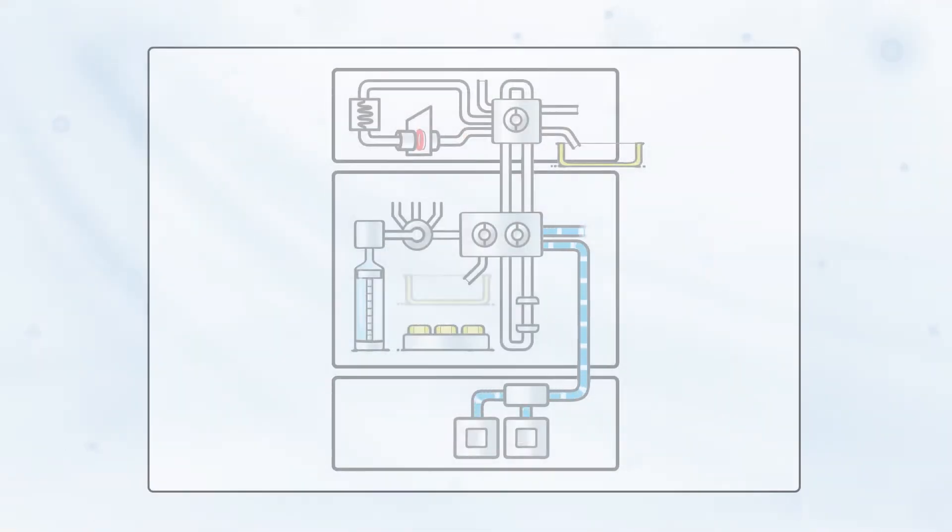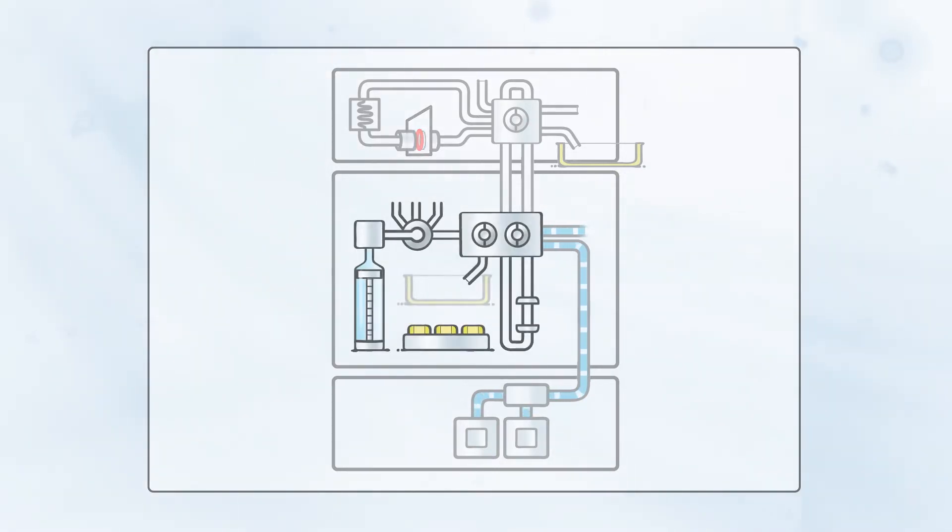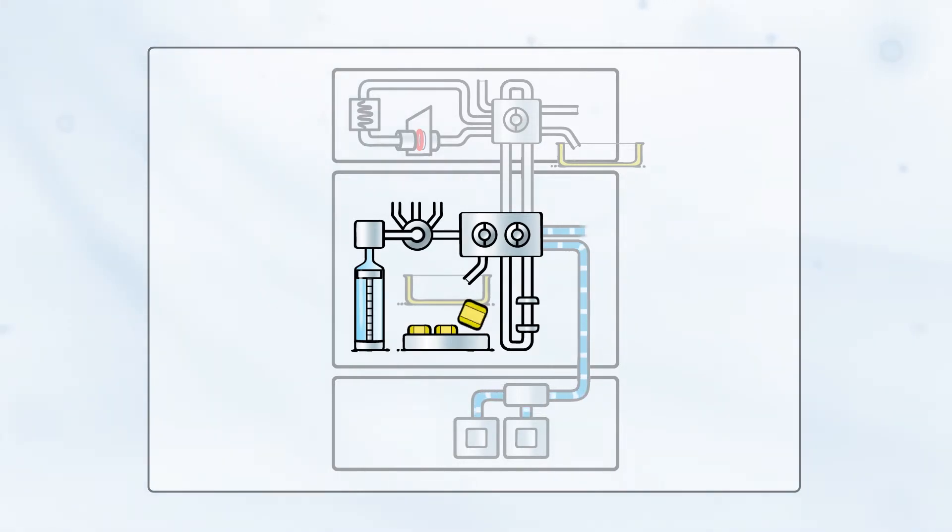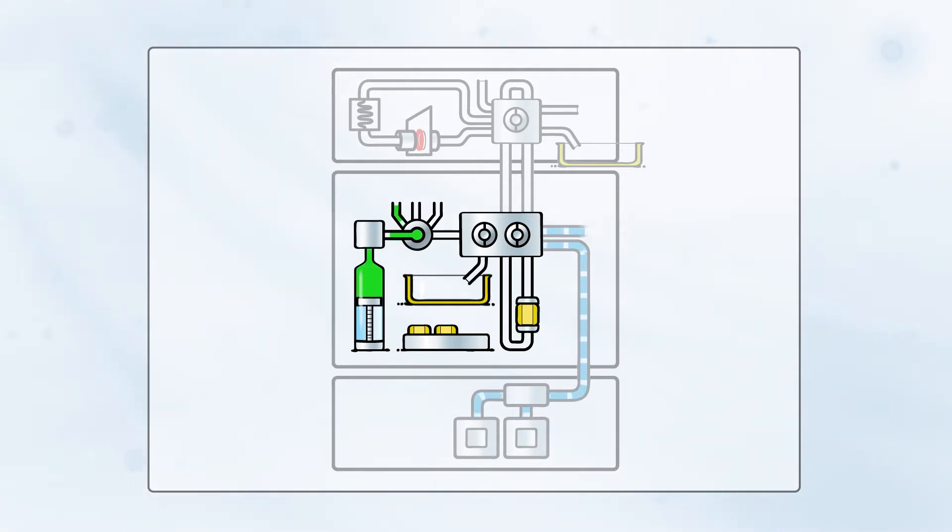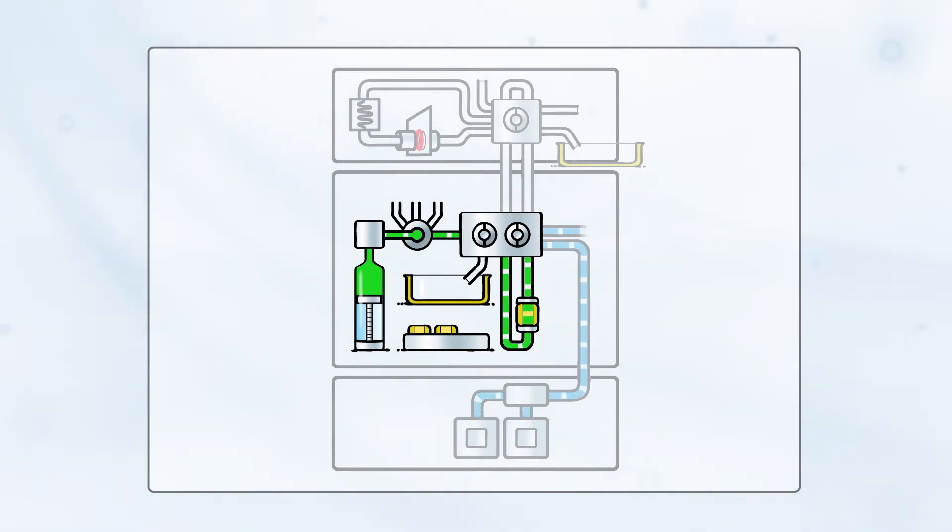Now, let's follow the blood sample on its way from dried spot to analytical result. First, a new solid phase extraction cartridge is automatically placed in the clamp. Conditioning solvent is aspirated by the high-pressure syringe and directed through the cartridge to condition the SPE sorbent for extraction.